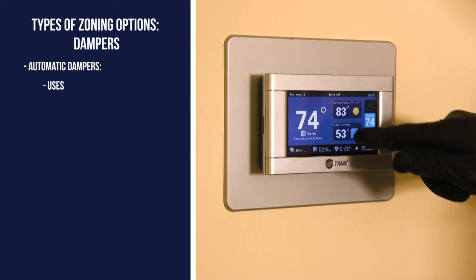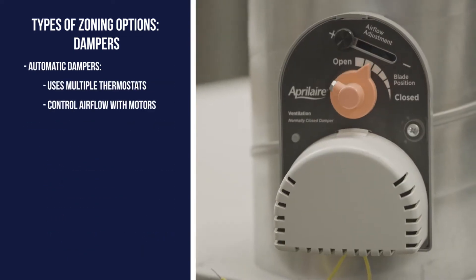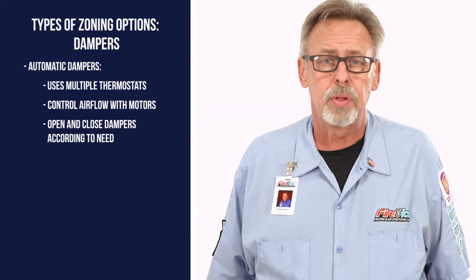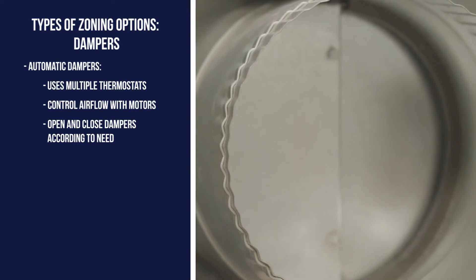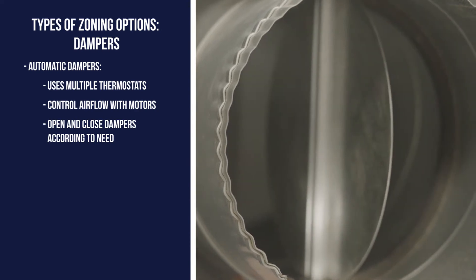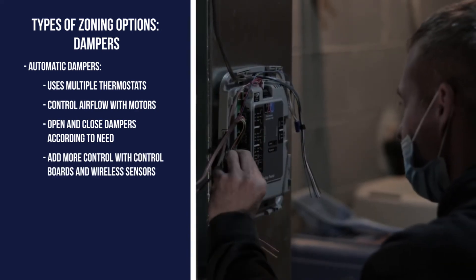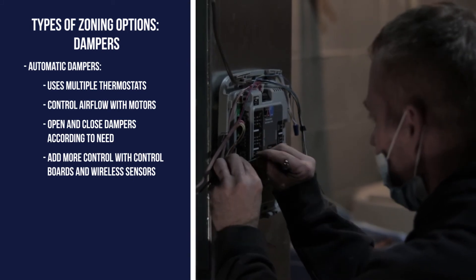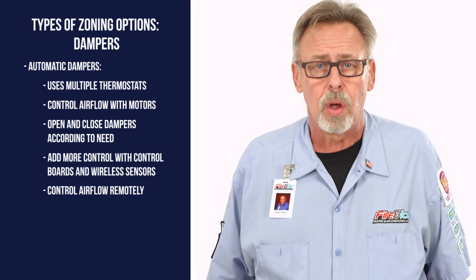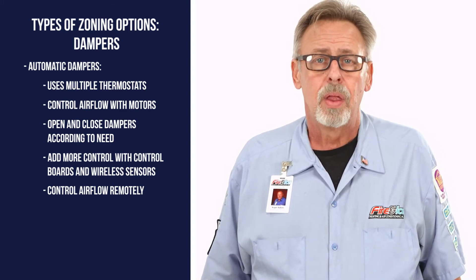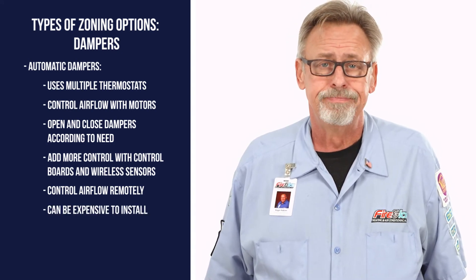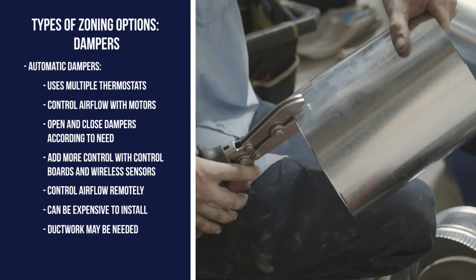Automatic dampers are controlled by multiple thermostats and use motors to control the flow of air. Each system can open and close the dampers according to how much heat or cooling is needed per zone. For example, if not much cooling is needed, the damper will only open partially, or if a lot of heat is in demand, the damper will open all the way. Additionally, control boards and wireless sensors can be used to give you even more control. The benefit of automatic dampers is that they can be controlled remotely and offer a better level of overall temperature control. The downside is that they are more expensive, maintaining them can be costly, and ductwork modifications may be needed to install them.